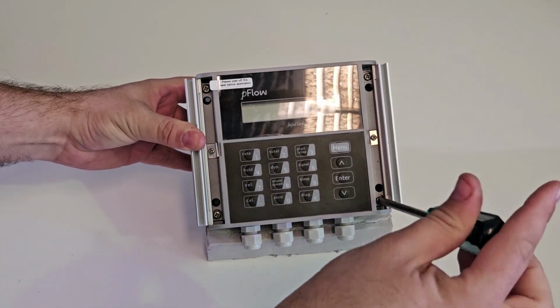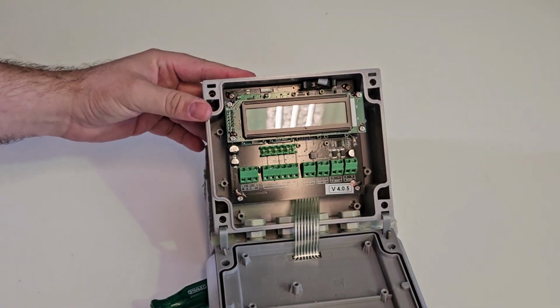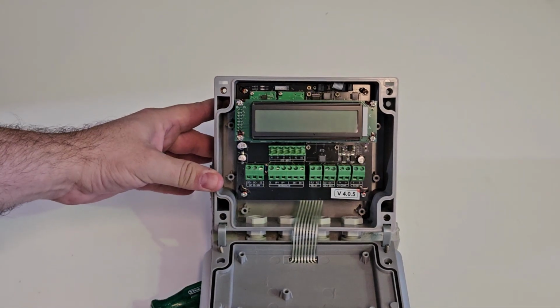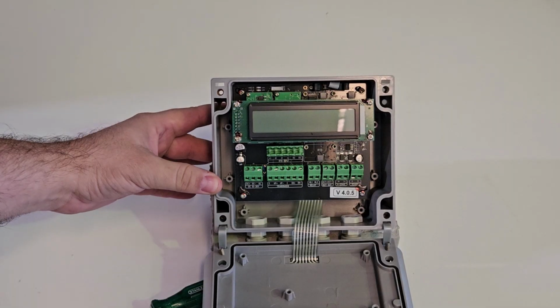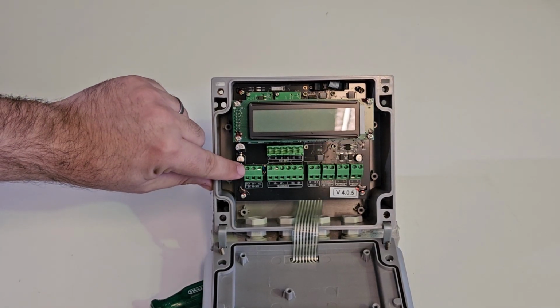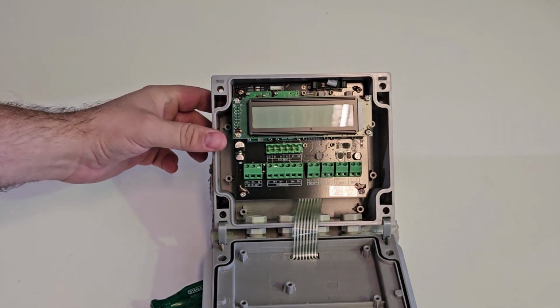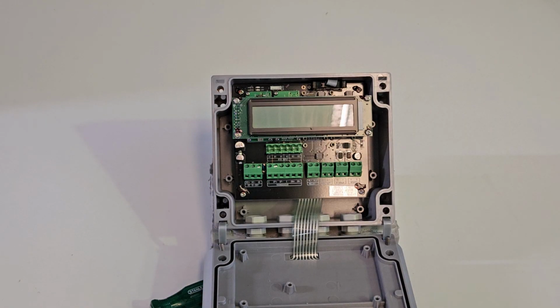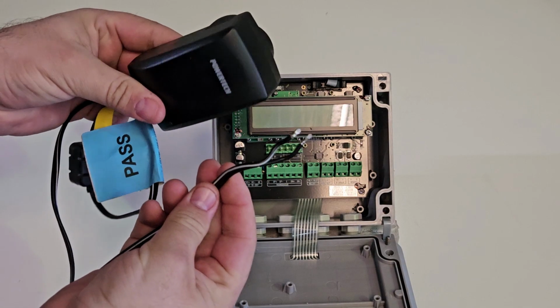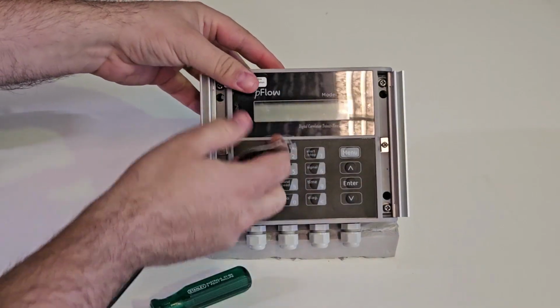Now open the flow meter, it hinges on the bottom. Now you can connect the wiring. In this example, we will just connect a 12 volt DC power supply here, and the upstream and downstream sensor cables, but there are various other connections for various inputs and outputs which you can refer to the manual for more information on. Take your power supply, then feed the wires through the left side cable gland.